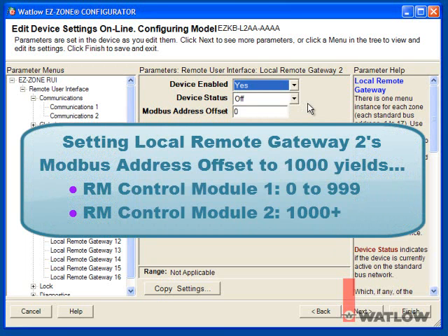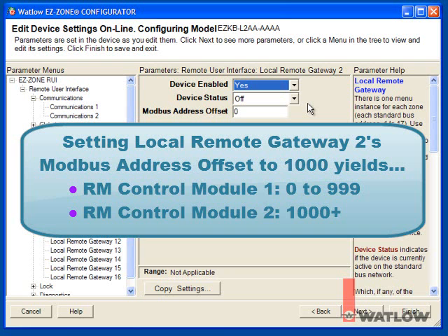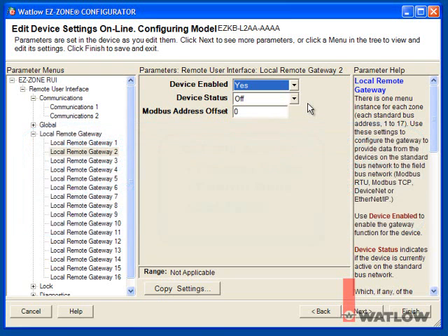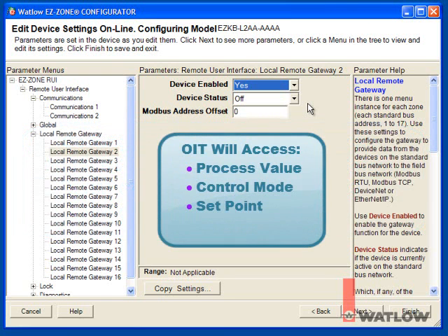For example, if we set the second controller's offset to 1000, only addresses 0 to 999 will be accessible in the first controller, and the second controller's data will start at address 1000. In this tutorial, we'll set up the gateway to allow access to the process value, control mode, and set point for loops 1 to 3 in both the RM control modules.